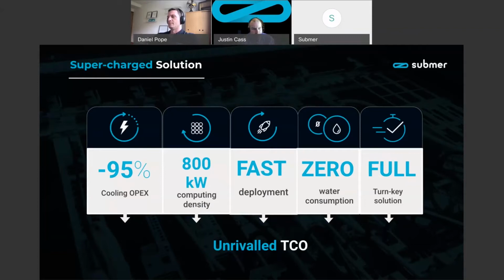Whereas with immersion, every single tank we add is pretty easy math. For a 50 kilowatt tank, every smart pod adds 50 kilowatts. If you go higher density, in the 100 kilowatt plus range, we can get up to 800 kilowatts very easily within a single modular deployment.